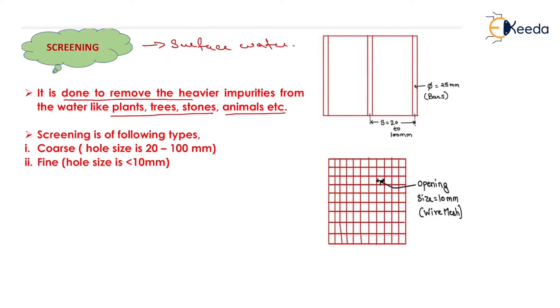What are the types of screen used in the screening process? There are two types of screen. The first one is the coarse screen, which is also known as the trash screen. It is generally made up of bars of 25 mm diameter, having center-to-center spacing of 20 to 100 mm. The next one is the fine screen or mesh screen, which has an opening size less than or equal to 10 mm.